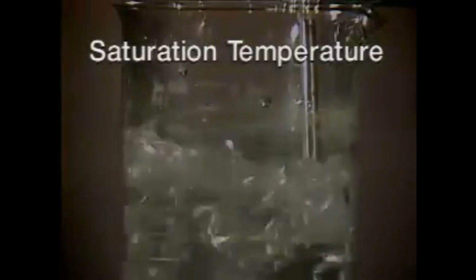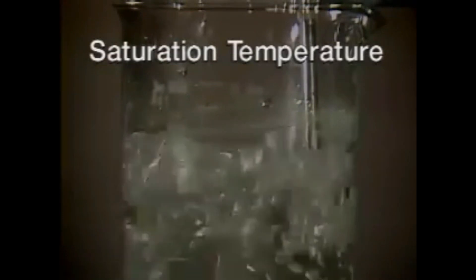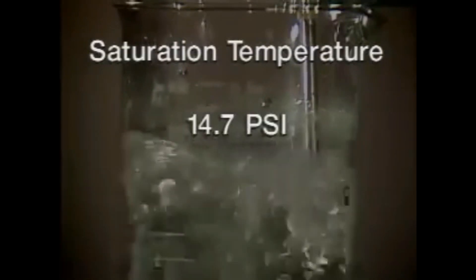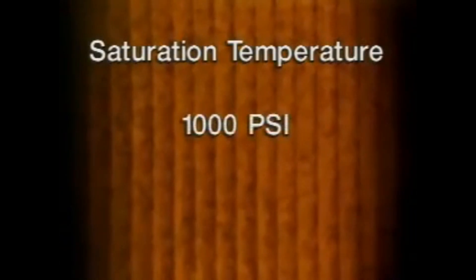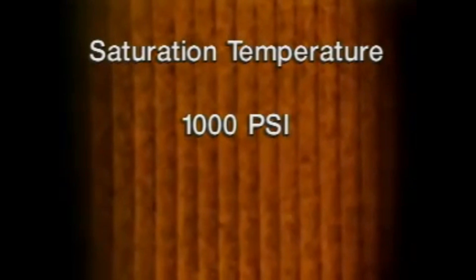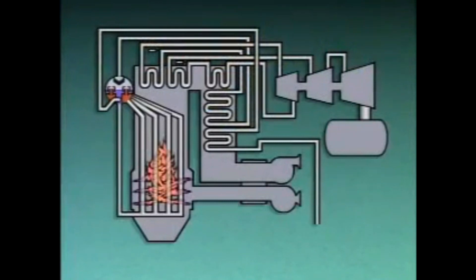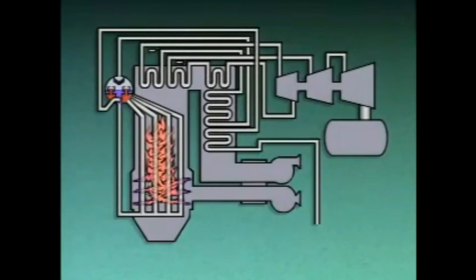As pressure increases, saturation temperature also increases. For example, at sea level, atmospheric pressure is 14.7 pounds per square inch. At that pressure, the saturation temperature of water is 212 degrees Fahrenheit. At a pressure of 1,000 pounds per square inch, the saturation temperature of water rises to 545 degrees Fahrenheit. When boiling occurs, as in this water wall, both water and steam are present and at saturation temperature. No matter how much heat is added to the boiler furnace, the temperature in the water walls will never rise above the saturation temperature as long as water is present.